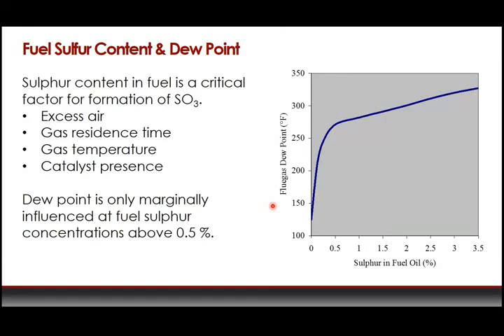Dew point is only marginally influenced when the fuel sulfur concentration goes above 0.5 percent or 5,000 ppm. In the graph showing dew point temperature versus sulfur content of fuel, below a half of a percent is where you get the largest rise. Once you get above a half a percent, the dew point is still going up, but at a very slow rate — so this lower range is the area of most concern when talking about sulfur content influencing the formation of SO3.